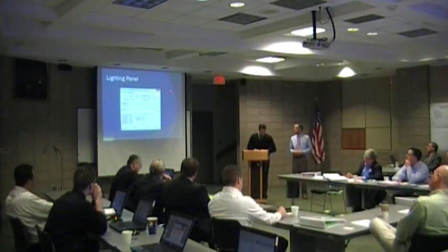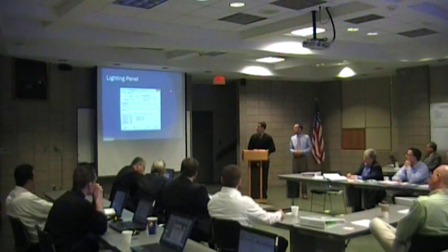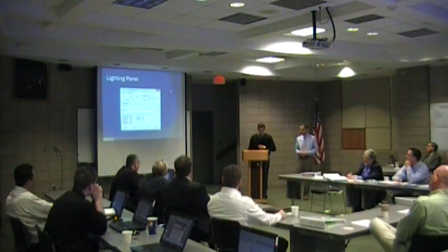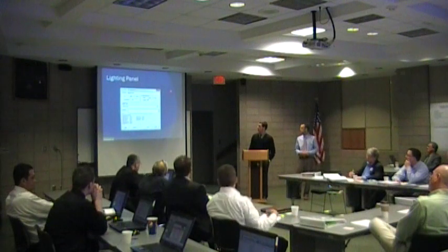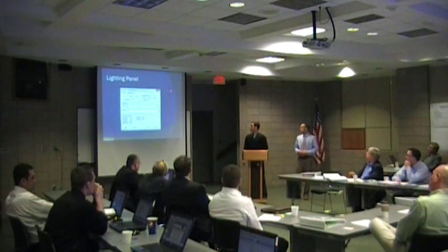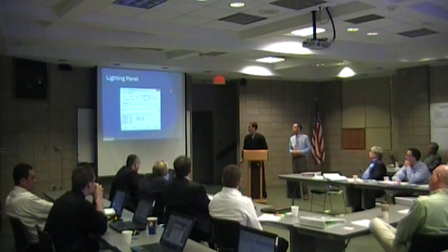This is a snapshot of the lighting panel and how we entered it into the software to size it. There were a few things we had to enter in. One was the running KVA, which you can see was 67, and also that it was a 208 three-phase load.